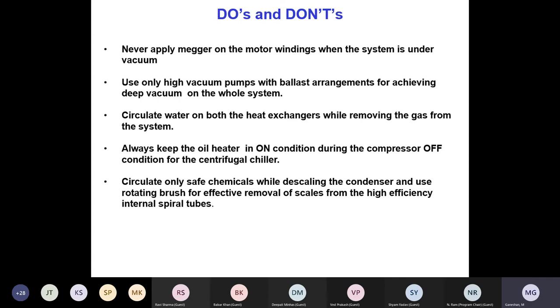Because the higher the temperature of the compressor oil, the lower the oil miscibility becomes. That is why we always keep the oil warm. Circulate only safe chemicals while descaling the condenser, because if there is too much acid, it can eat away your condenser tubes. Always use a rotating brush when descaling, because nowadays high efficiency tubes are internally grooved, and to clean them you should use a rotating brush.